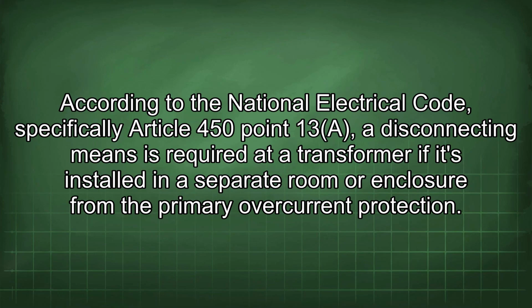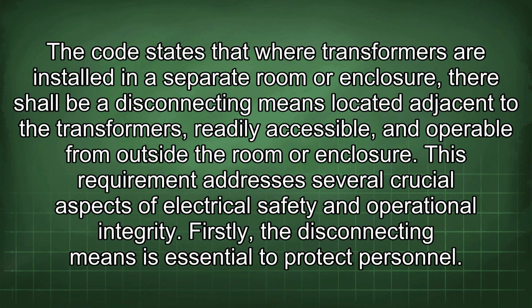According to the National Electrical Code, specifically Article 450.13(A), a disconnecting means is required at a transformer if it's installed in a separate room or enclosure from the primary overcurrent protection. The code states that where transformers are installed in a separate room or enclosure, there shall be a disconnecting means located adjacent to the transformers, readily accessible and operable from outside the room or enclosure.